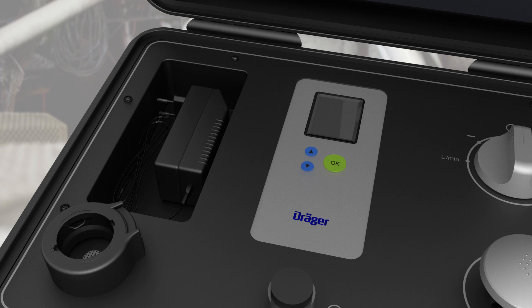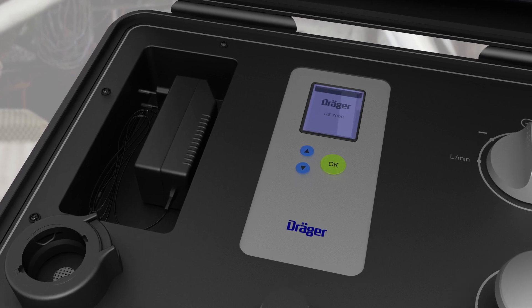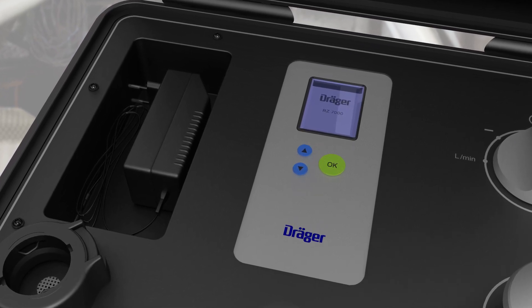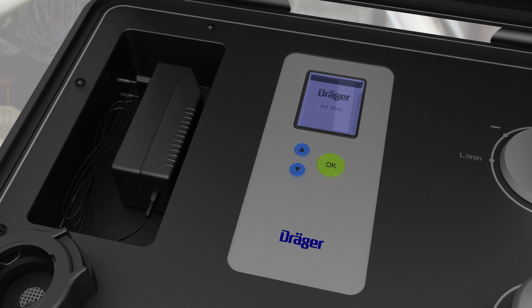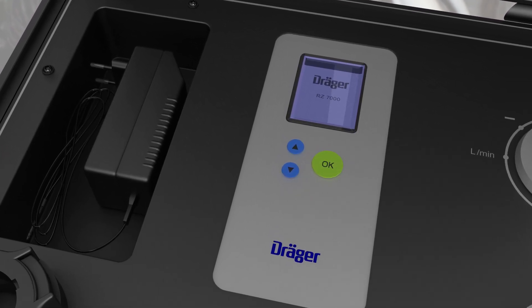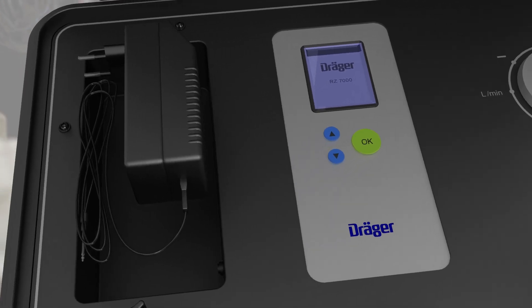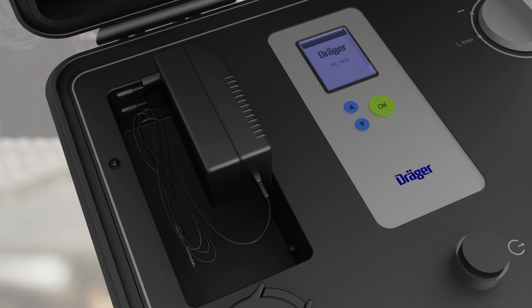You can count on the RZ7000 being ready for use due to an attached lithium-ion battery capable of continuous testing for up to 24 hours. No more hassles with inconvenient test equipment. With the Draeger RZ7000 everything you need is at your fingertips, including the quick charger.